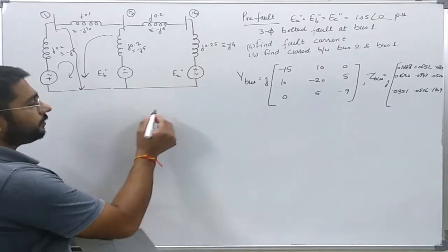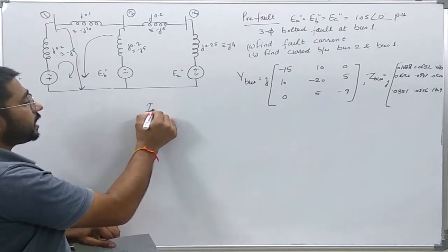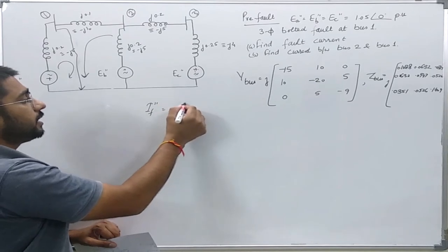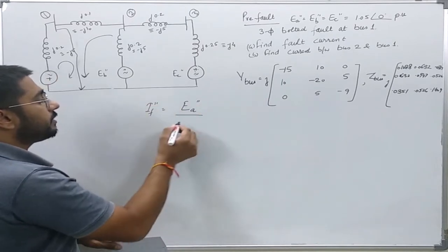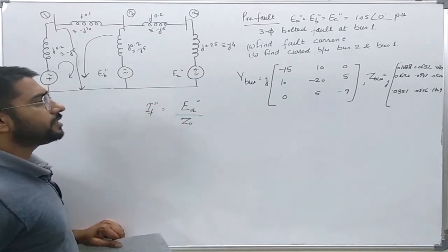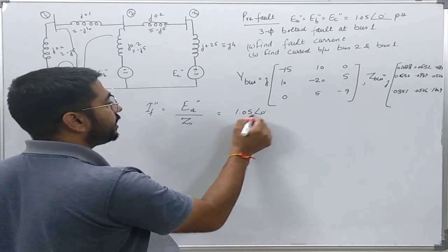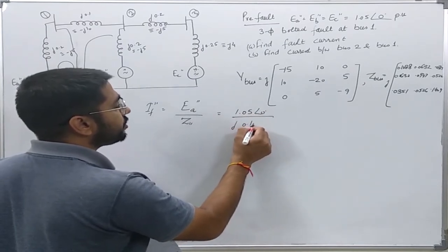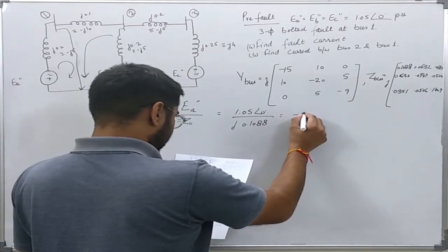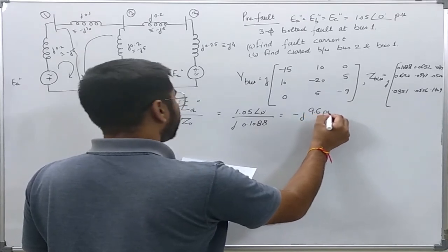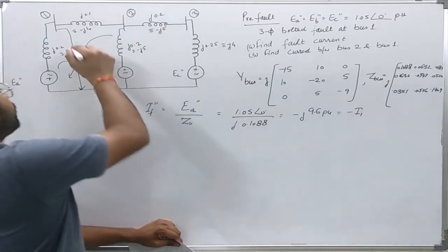We know that the fault current for a fault at bus 1 will be simply IF'' is nothing but the voltage at bus 1 before the fault occurred, equal to E_a'', divided by the Thevenin impedance at bus 1, which is nothing but Z11. So it is 1.05∠0° divided by j0.1088, and it comes out to be minus j9.6 per unit. I know that this is equal to minus of I1. I have found this current.